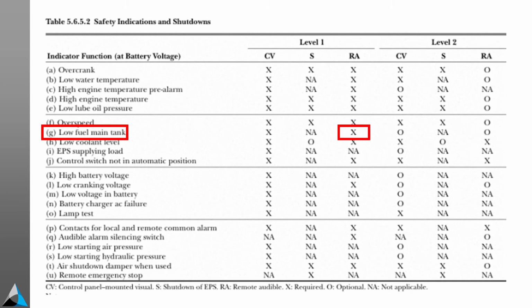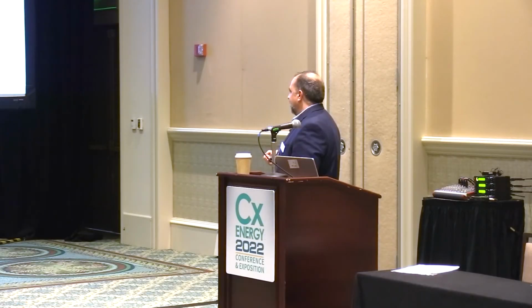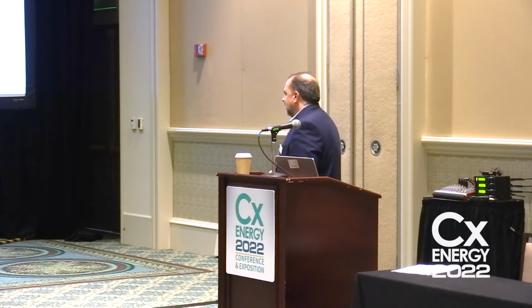That's the backup in case people ask where it says that's required. It's in NFPA 110, which lists what alarms are required to be part of the generator's remote annunciator panel, and low fuel in the main tank is certainly one of them. So I'm always looking for that, because it gets overlooked a lot.